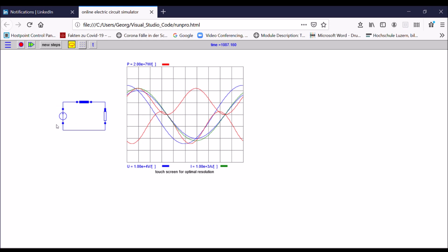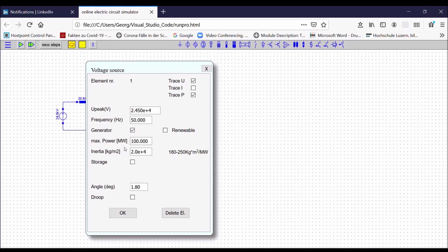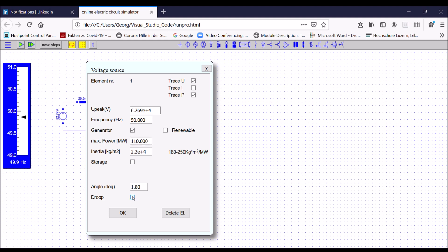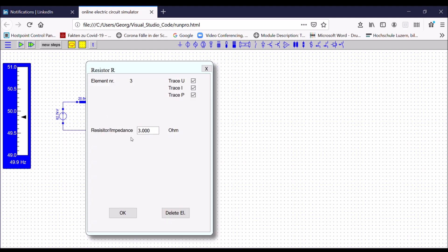The source I have here has a stiff frequency of 50 Hz. A real generator, of course, would be slowed down by the load, so the frequency would decrease. Therefore, I will change to a more sophisticated model — from a voltage source model to a generator model. I set the maximum power of my generator to 110 MW per phase and click on the droop, which is a speed control of the generator. In order to get 100 MW output as per nominal, I need a 3-ohm resistance, which results in a 100 MW load.